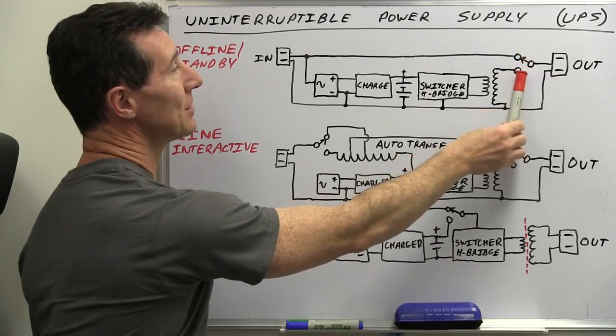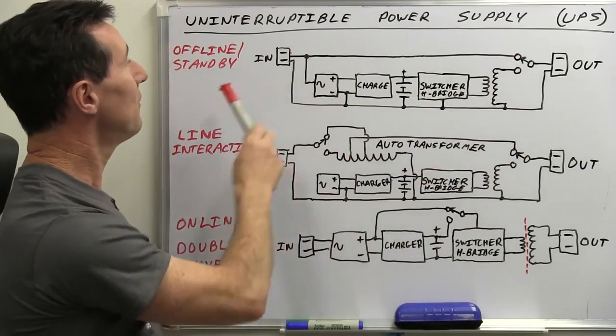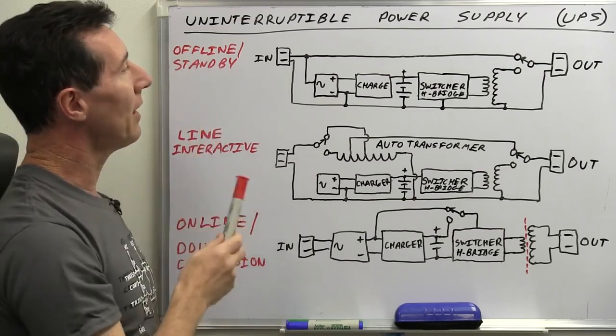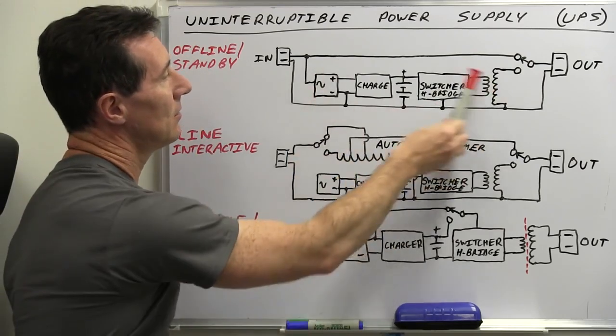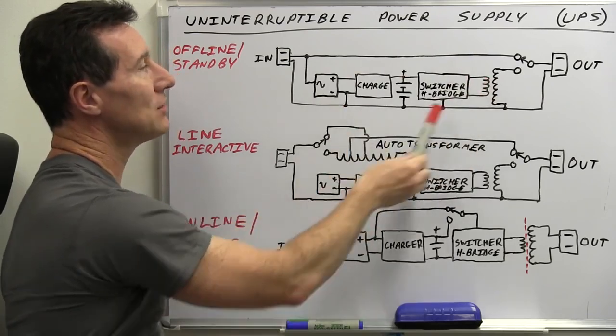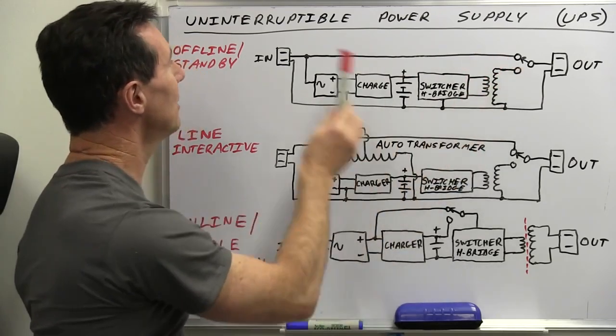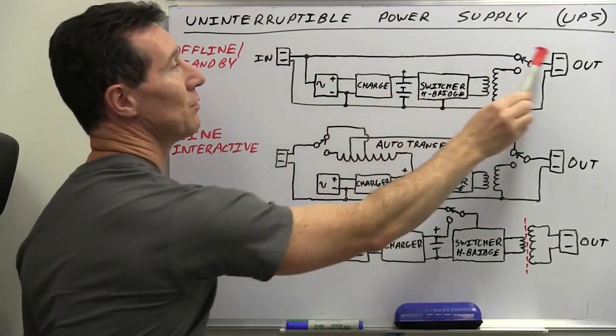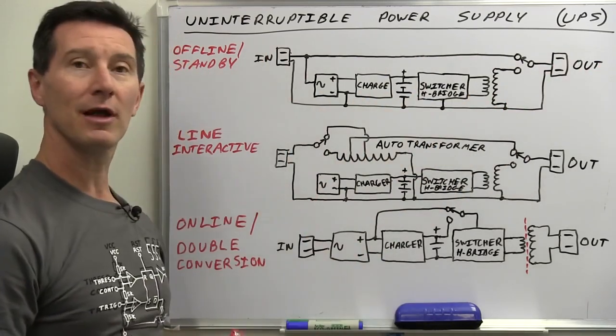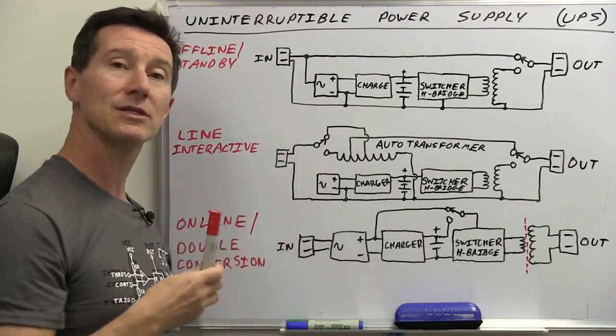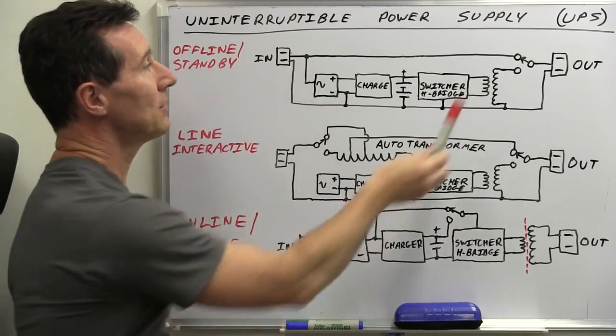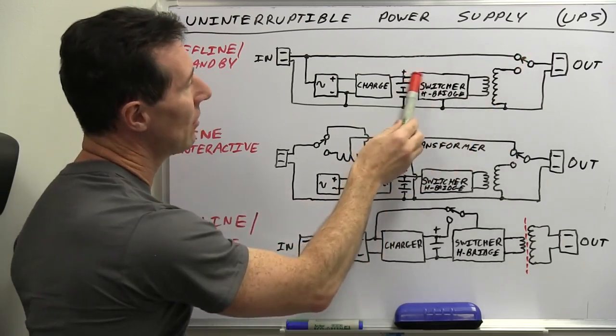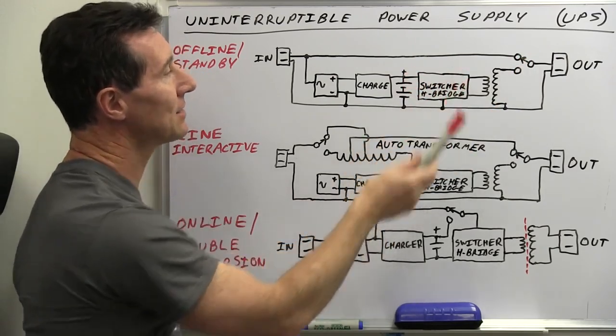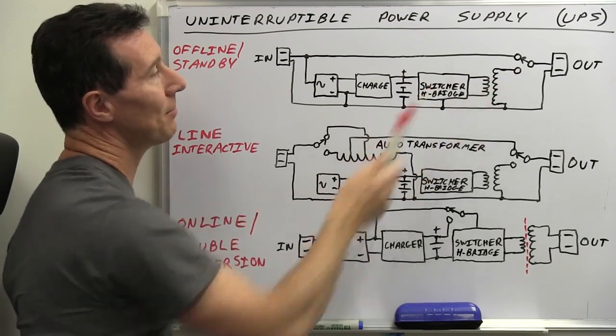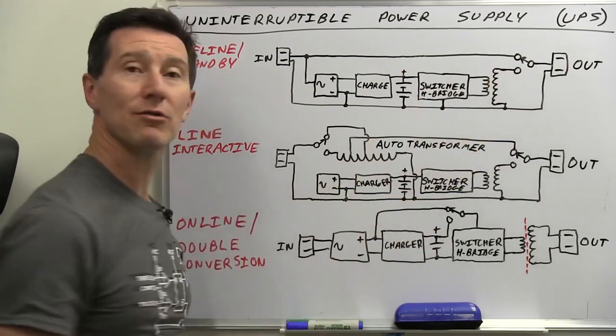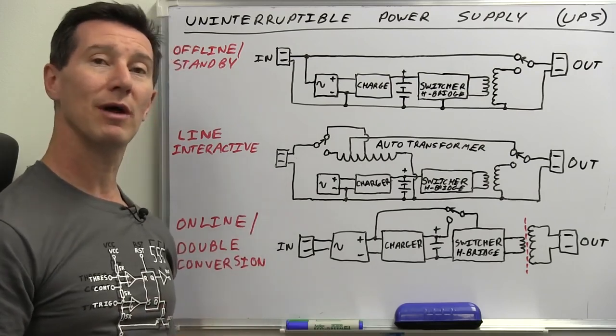And then there's a basic switch in here. By meaning offline, it means that the charger and battery part of it is usually offline, so it's switched out, and your AC is switched directly through to your output. So only when it detects that the main input mains power has failed does it rapidly switch over. I haven't shown any switch here, but it rapidly starts up the inverter, your step-up conversion, and generates your sinusoidal or square wave output voltage.